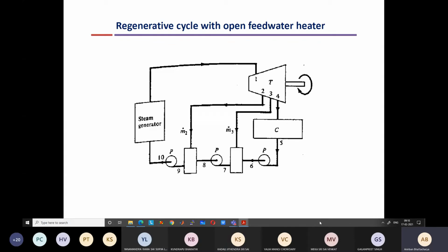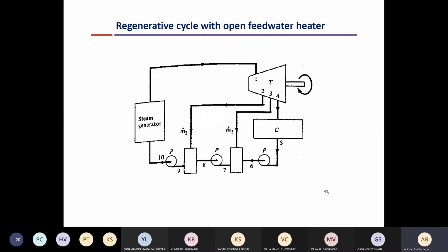Yes. Okay. So then the rest of this steam, say around 90%, passes through the other stages and gets expanded and goes towards lower pressure and temperature. After a few more stages, again, some of the steam is taken out and taken to a mixing chamber, which is another feed water heater. Okay. Again, the rest of the steam just goes on expanding, and whatever steam is left finally, which is the major portion of the steam, say around 70 to 80%, is taken out at low pressure and temperature after the final stage in the turbine. Okay. So this is passed to a condenser.